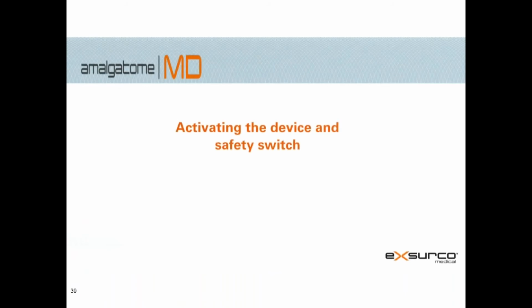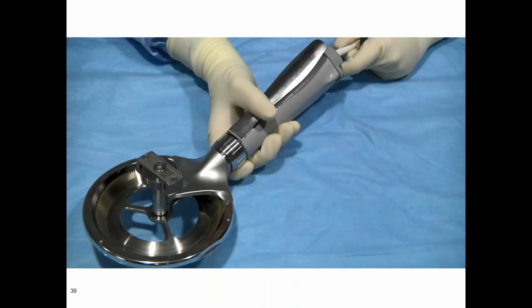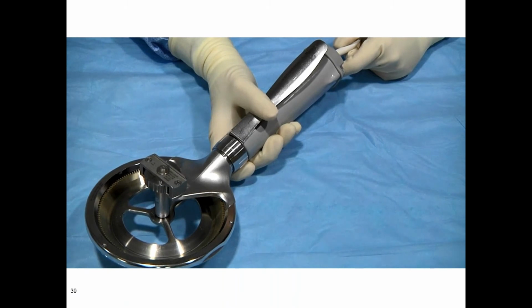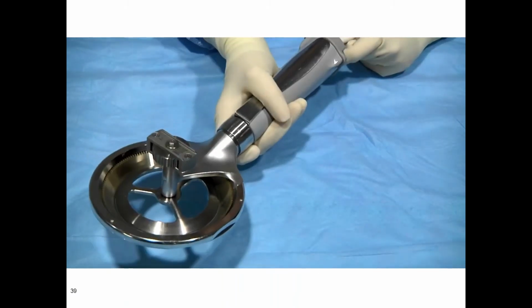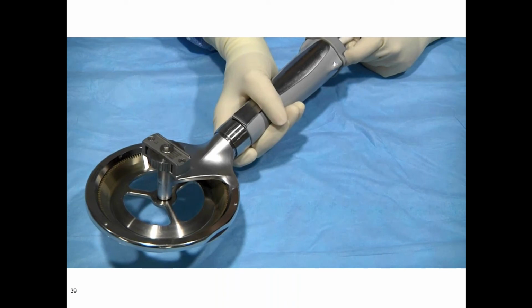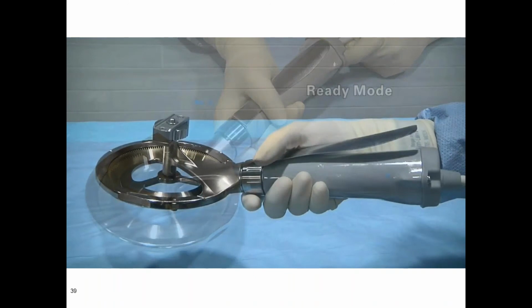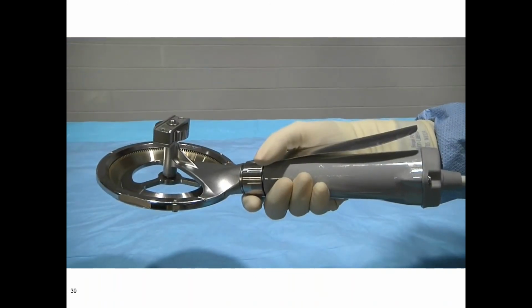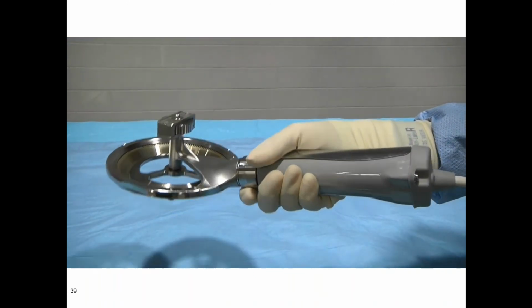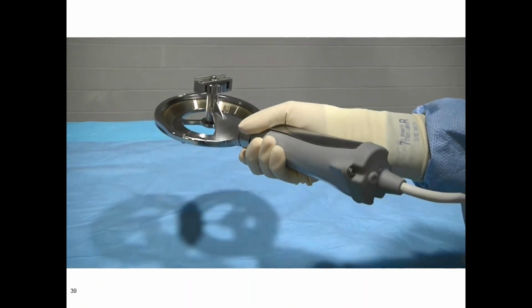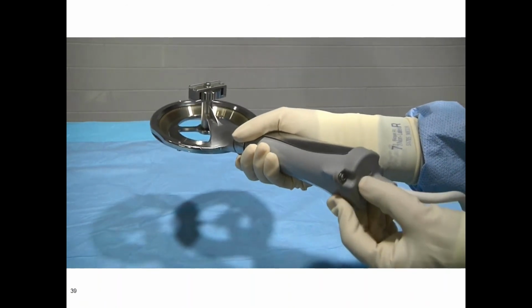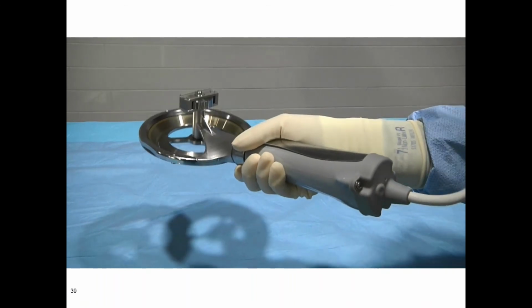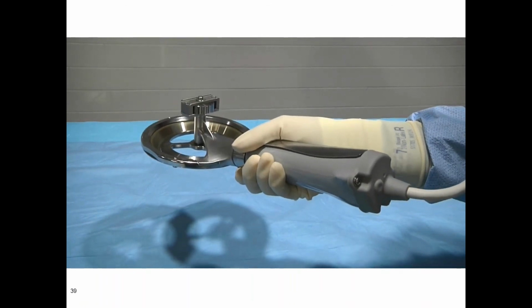Activating the device and safety switch. When ready to operate the Amalgatome MD, press the activation lever down onto the handle. This will put the instrument into ready mode. While the activation lever is depressed, a firm grip is kept on the instrument. Press the activation button located at the end of the handpiece next to the power cord. This will cause the blade to rotate.